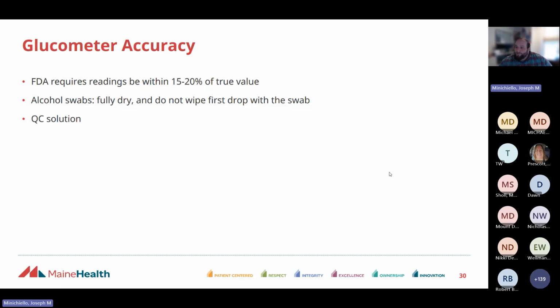So the FDA, in order to approve a glucometer, interestingly, only has to be within 15 to 20% accuracy of the true value. And so, if someone's actual sugar is 100, plus or minus 20% is plus or minus 20. So you're 80 to 120, you're fine. But if you're talking about 60 to 65, plus or minus 20% is plus or minus 12 or 15. I mean, you're talking about treatment thresholds. And then, yeah, if the device starts to fail, you're even further off.